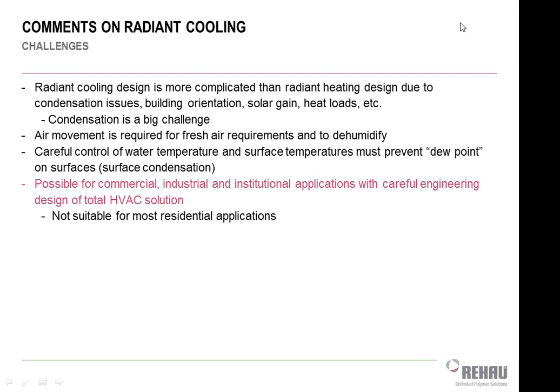A couple of comments on a few other systems here, one of which is radiant cooling. So not only can we heat a building by putting warm water through tubing in the flooring or ceilings or walls, we can also cool a building that way, right? So instead of sending 90-degree water through the tubing, we could send 50-degree water through the tubing, and that would cool the building off. Although if I send 50-degree water through there, chances are pretty good that would be below the dew point many times a year, and that would probably cause condensation, and you obviously don't want condensation on your floor. So if you're going to do a radiant cooling system, there are lots of design considerations in regards to controlling dew point. For one, it typically means my radiant cooling water is going to be fairly high, 56, 57, 58, 59 degrees, something like that, so that I don't go below the dew point.